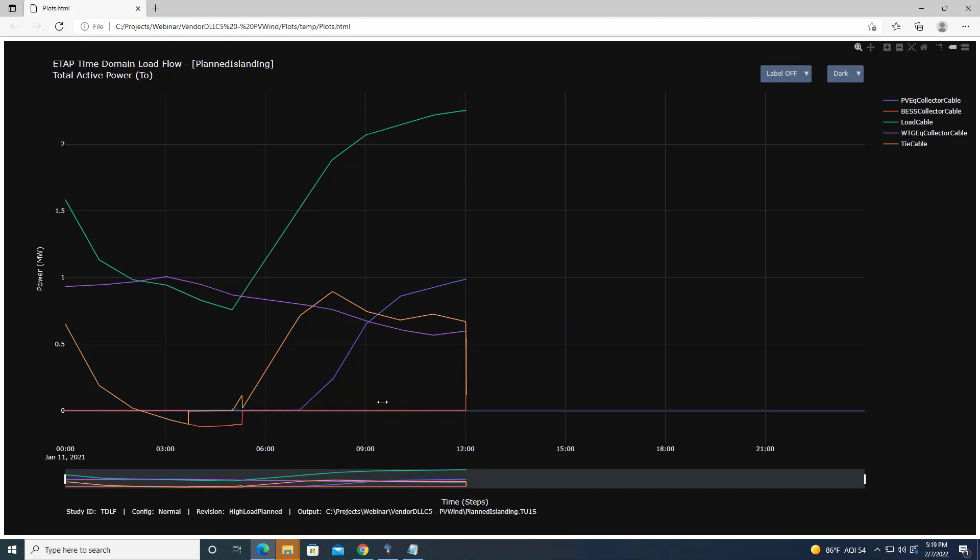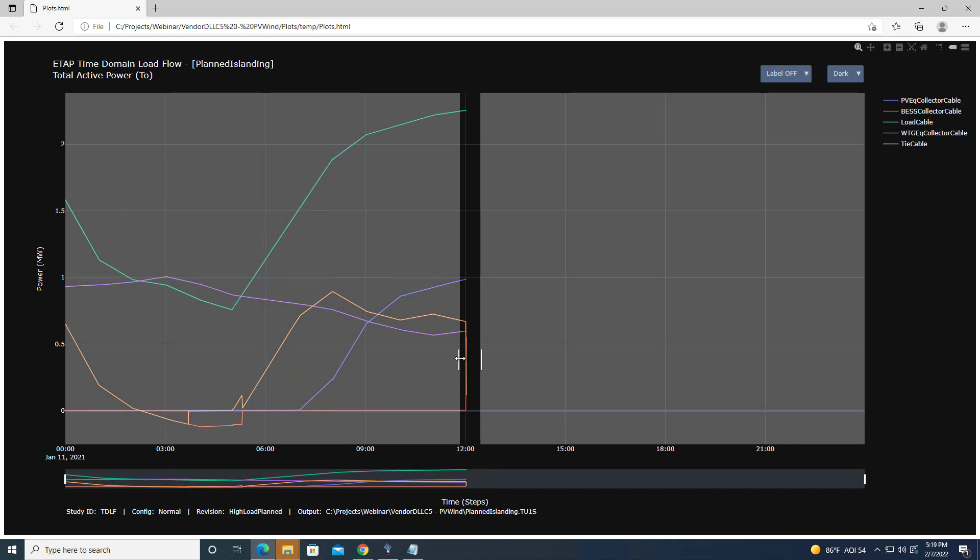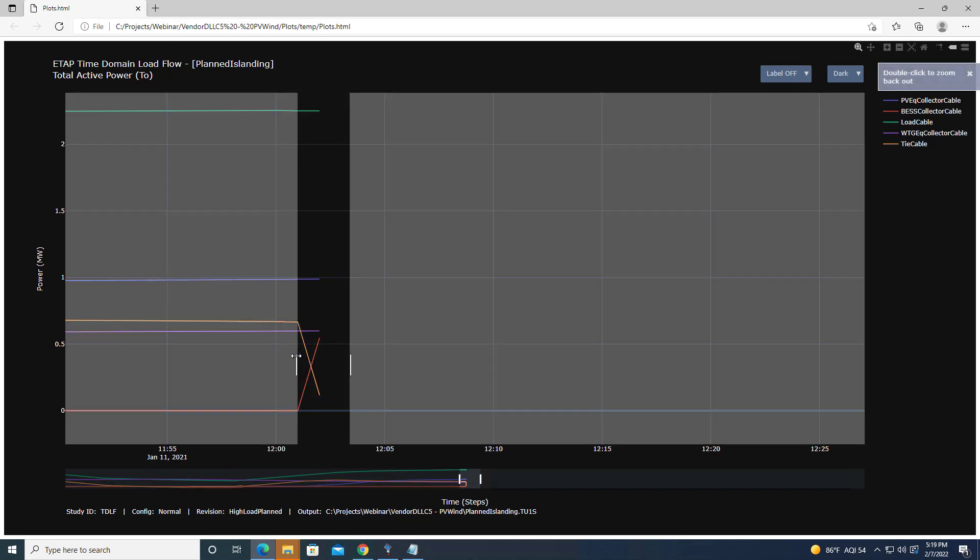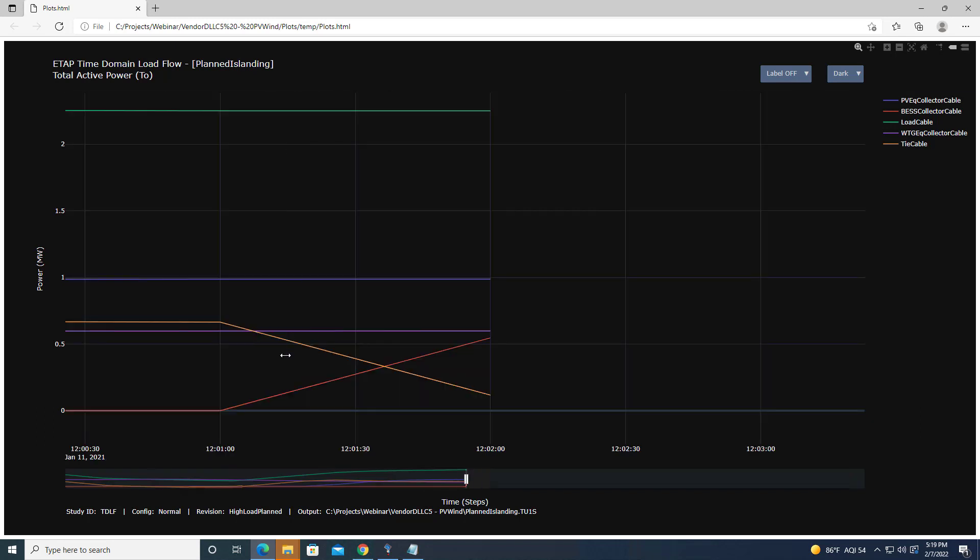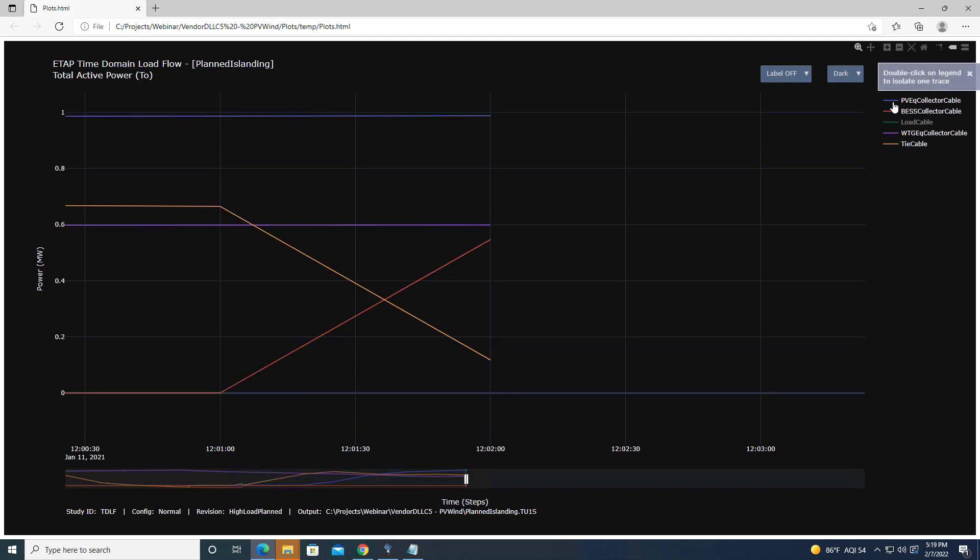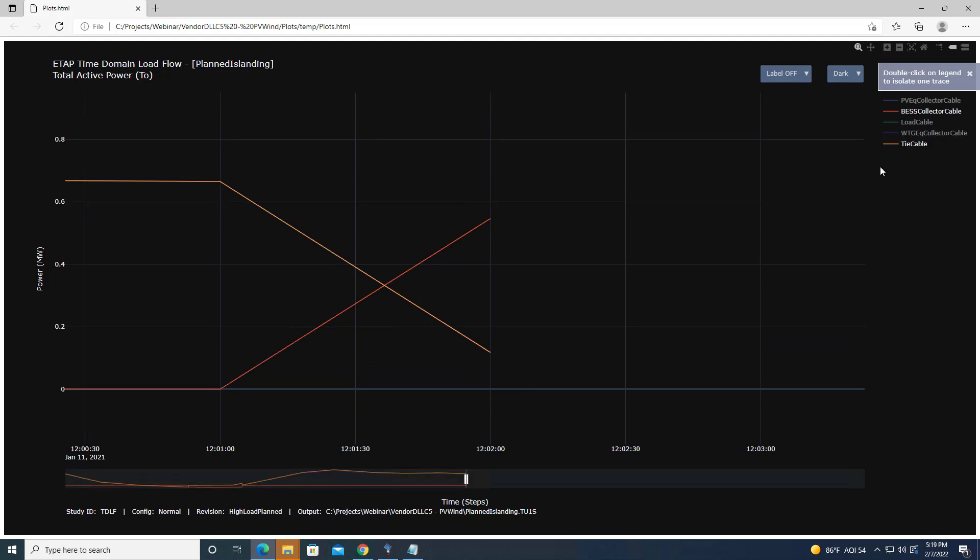The key point is that a few minutes before entering islanded mode, the microgrid controller increases battery power. This brings down the active power at the tie cable. As you can see, when the battery power goes up, the tie cable power comes down.